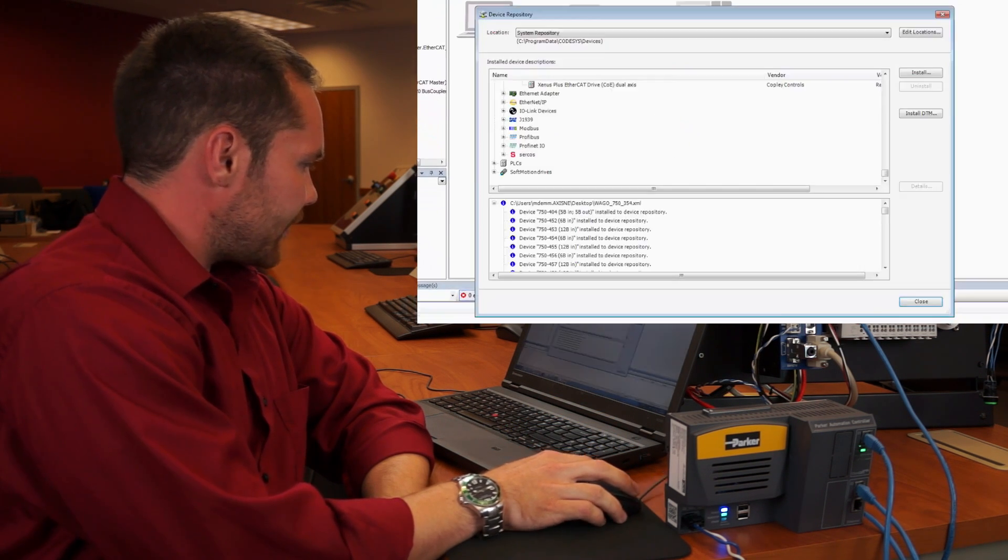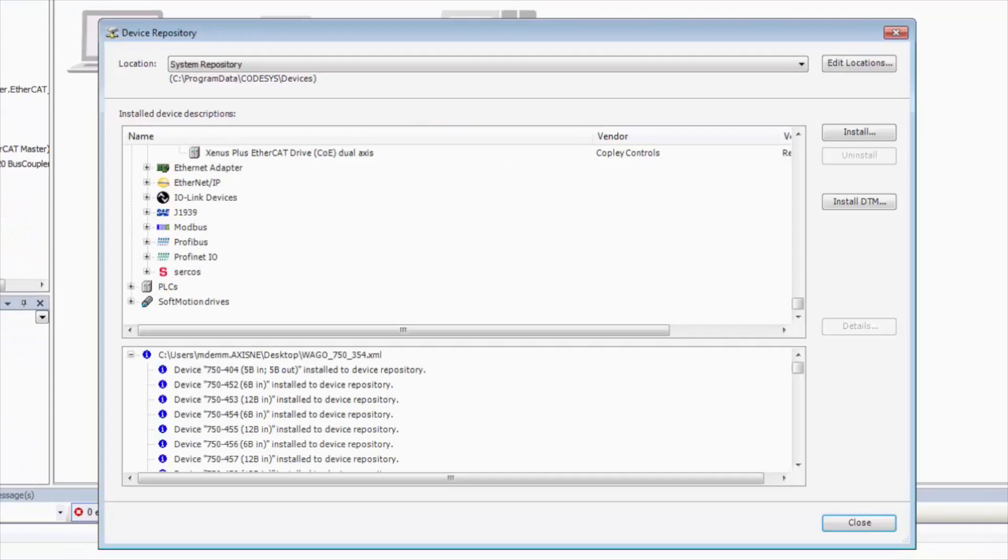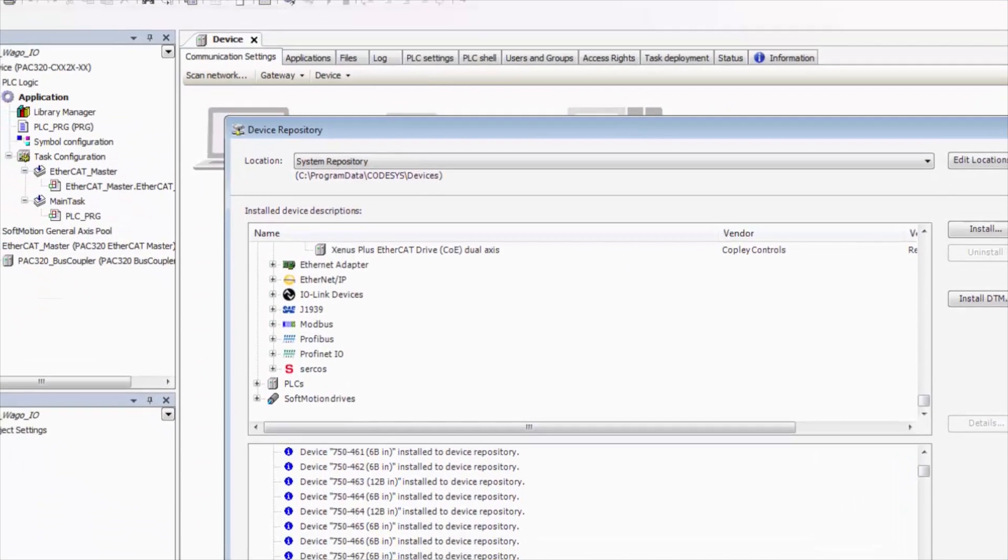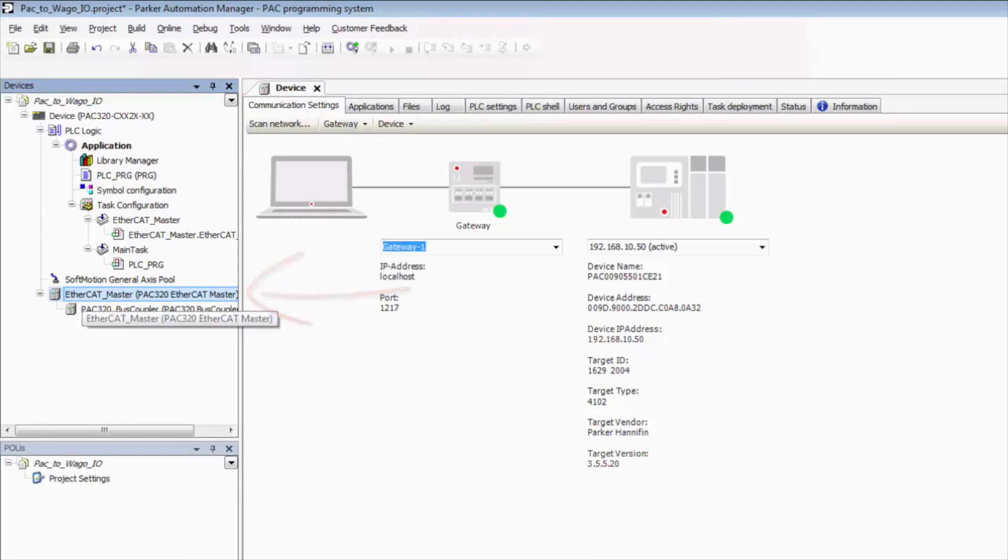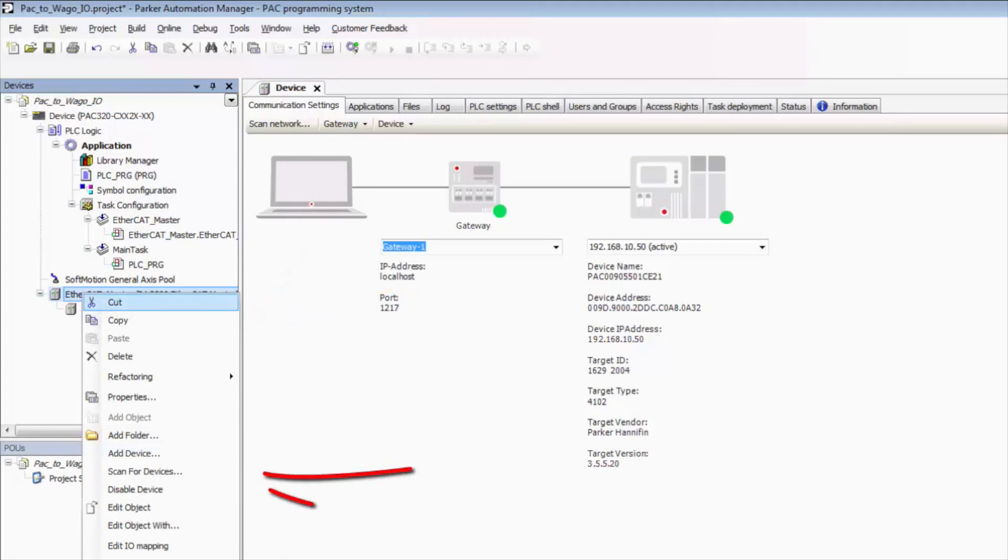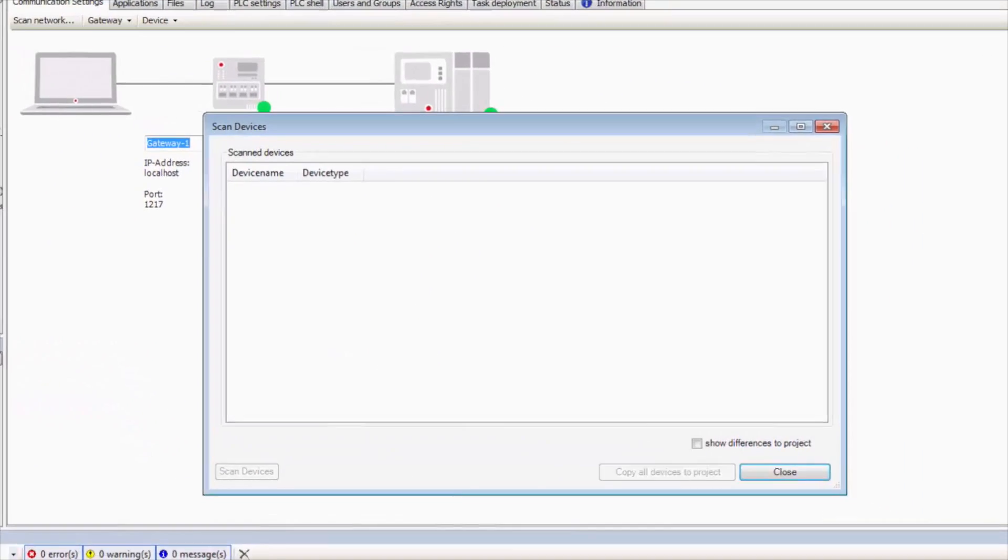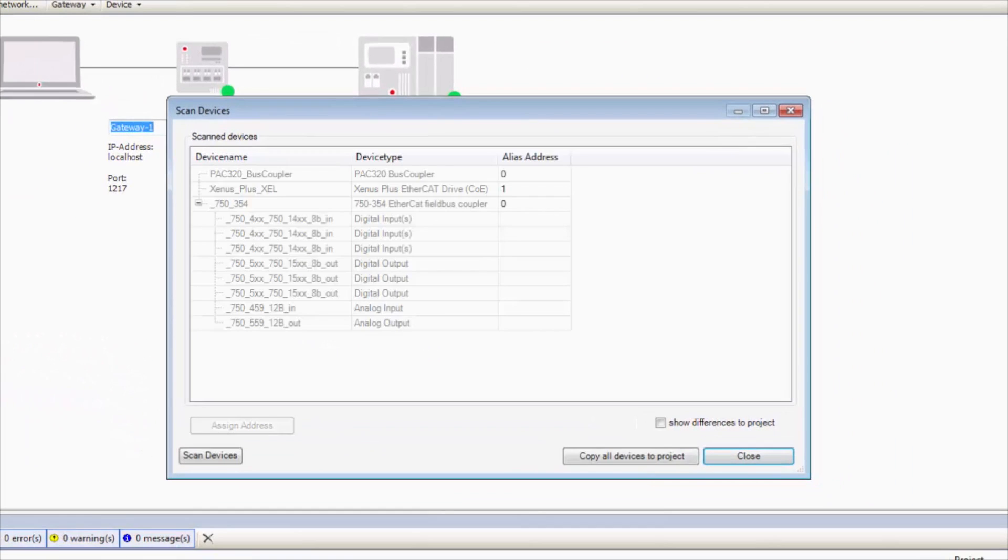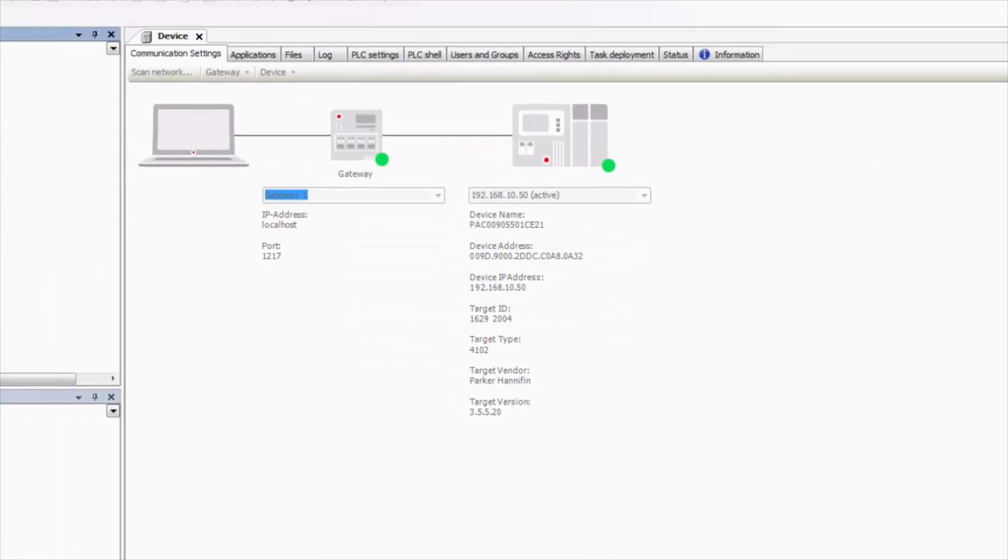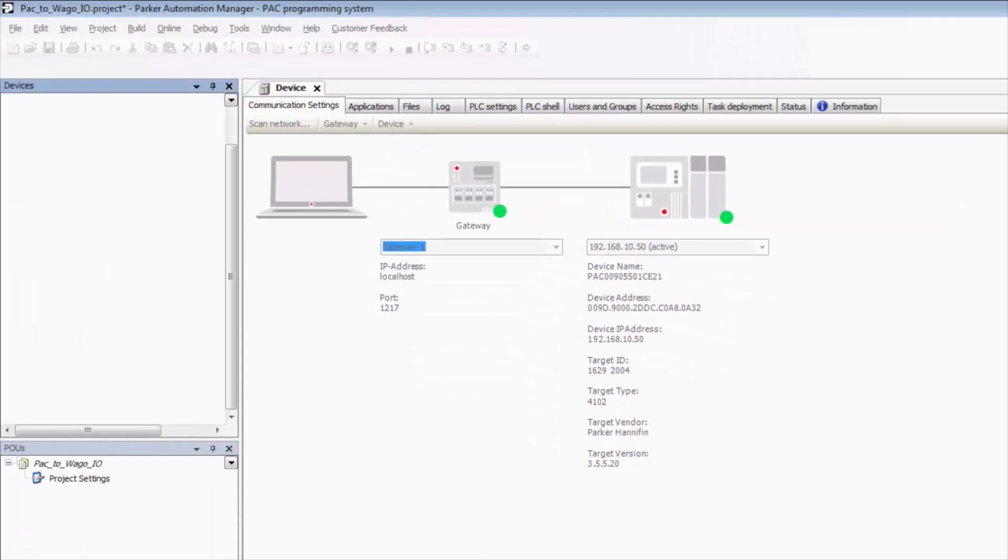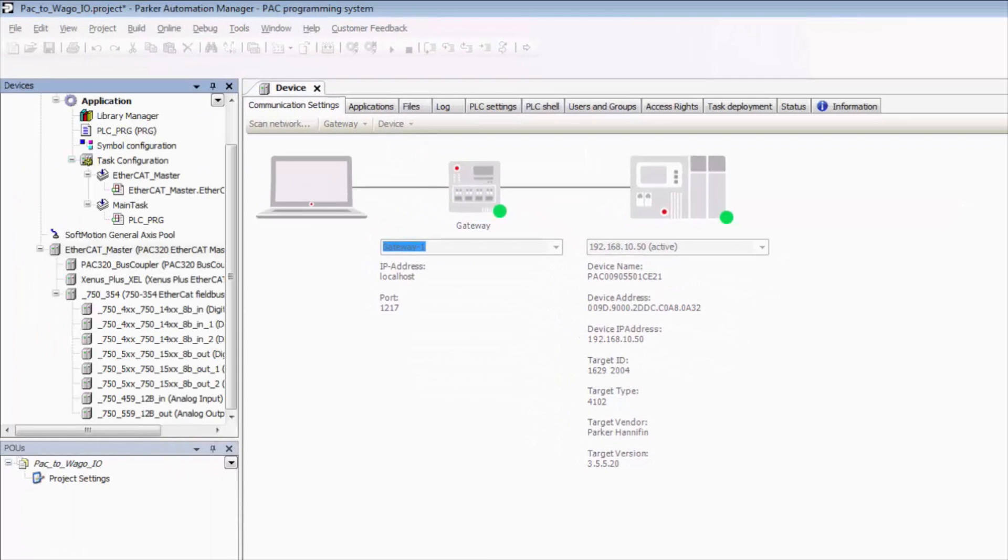Now that that's completed successfully, we can close that, click EtherCAT master again, right click, go to scan for devices, and now we see that we've found our WAGO EtherCAT IO coupler. Now all we need to do is unselect that, click copy all devices to project, and it's going to add our drive and our IO to our project tree.